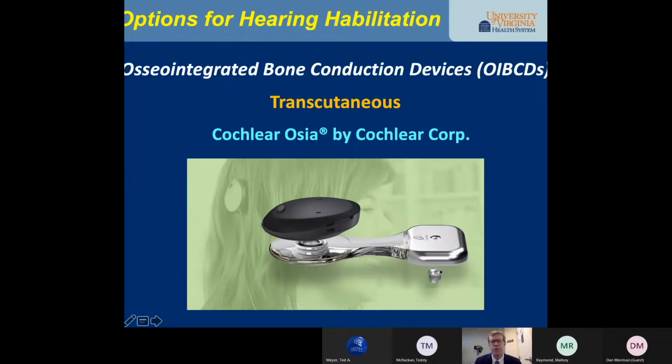The Cochlear Osia works on the same implant platform as does the Baha Attract and the Baha Connect. Rather than attaching the abutment or the magnet to the implant, now we're attaching the mass transducer. Now we're attaching the active transducer. So this is the active part. You still have a microphone and transmitter that's worn on the outside. The sound energy goes through the induction coil to the receiver stimulator that then stimulates the active part directly connected to the implant that's integrated into the bone.